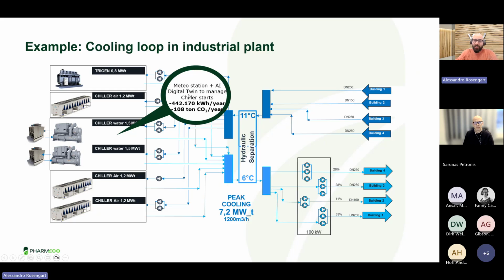With a bit of control system based on a meteo station, we can understand when there is the peak of heat from the weather and the peak of the need for cold, monitoring the plant. Together we optimized the pattern of operation of the chillers, running them on demand while still keeping 100% availability as before. This resulted in some 108 tons of CO2 saved per year, and a huge amount of 442,000 kilowatt hours per year.